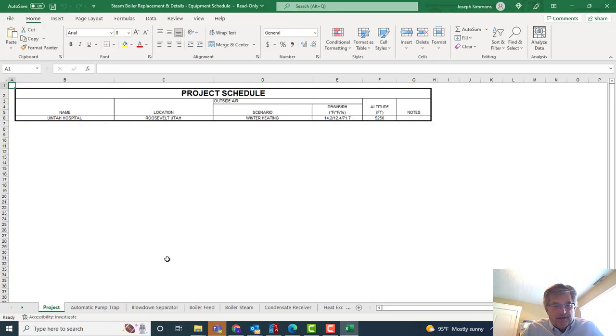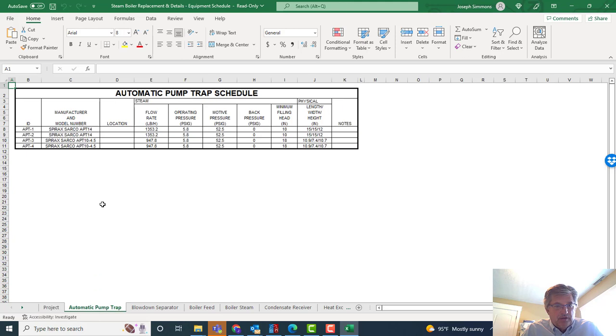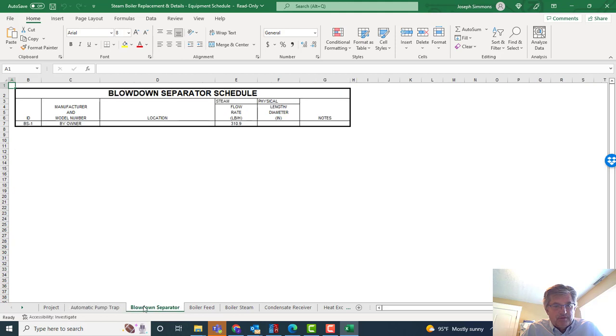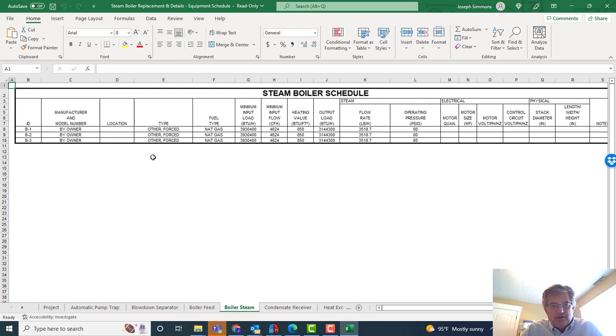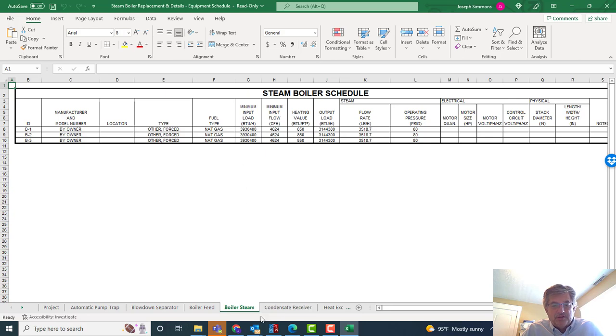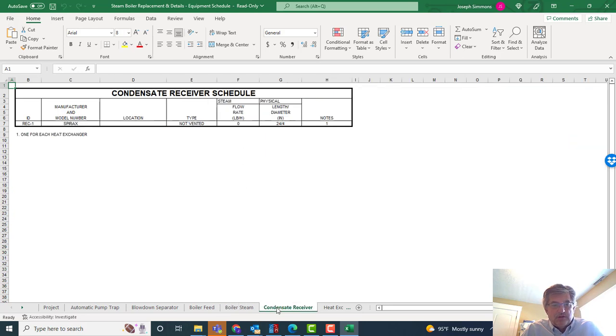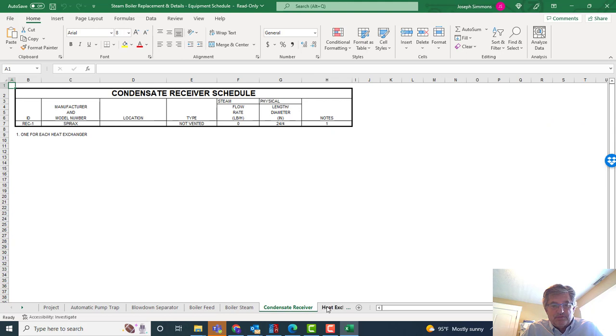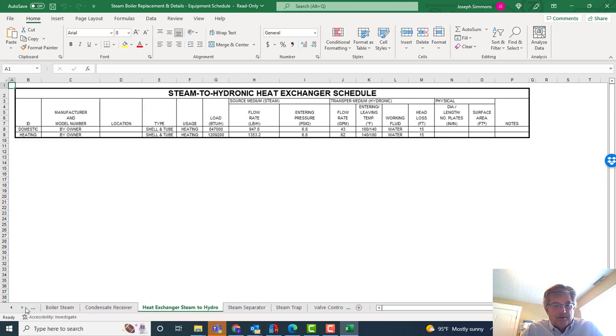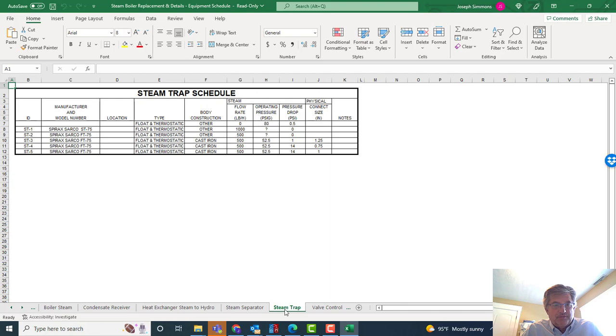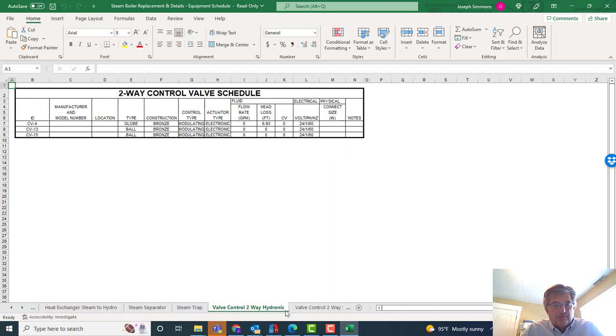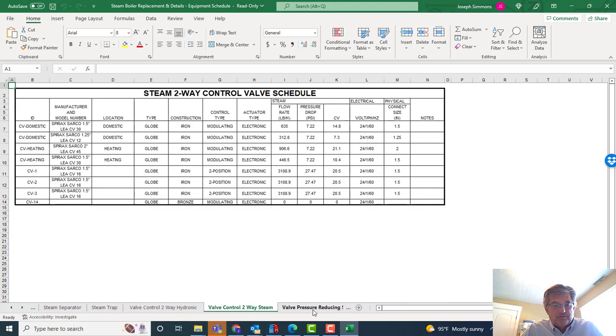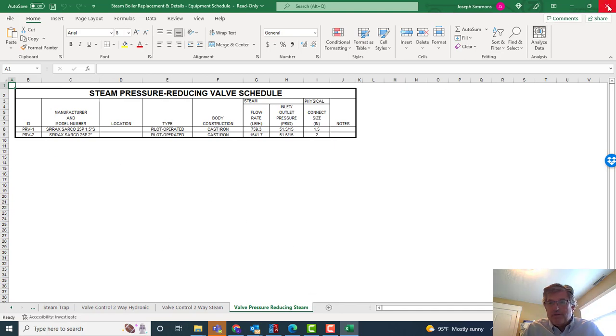Here's my equipment schedules. This would have the capacities. That was the hospital out there in rural Utah. The pump traps, capacities what they were. The owner knew what to get. The blowdown separator, steam capacity, boiler feed, capacities, voltage. The steam boilers—you see they were just over, almost 4 million BTUs there, each one. Receiver, heat exchangers, steam separators, steam traps, control valves, PRVs, all equipment, major equipment right there.